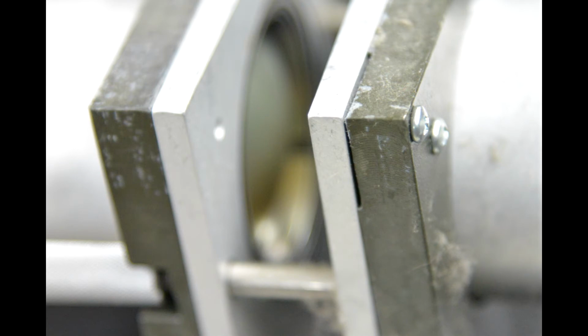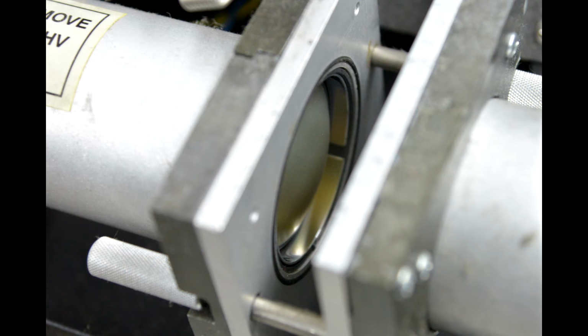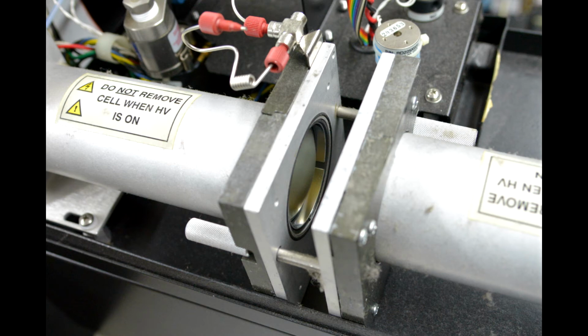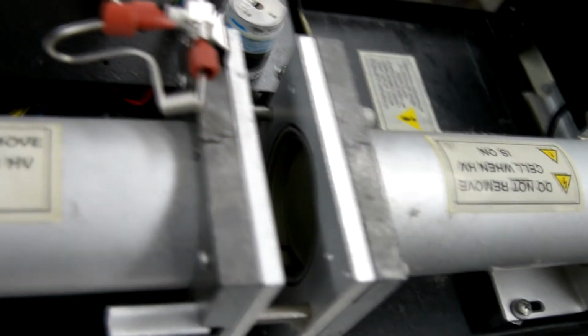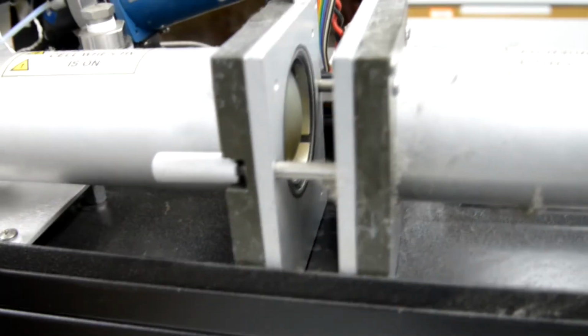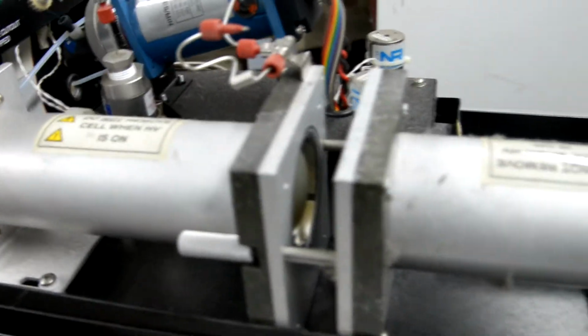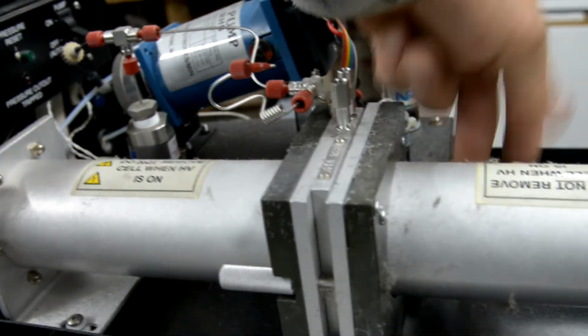You have two photomultipliers, one on the left, one on the right, and you have a space between them. The dark piece of metal is the lead base neck that will go to the shielding. There is an O-ring made of rubber. When you squeeze those two photomultipliers together, it does not allow any light to go in. The high voltage is delivered from each side of that housing to the photomultiplier tube, and the BNC connector allows the signal to go out.